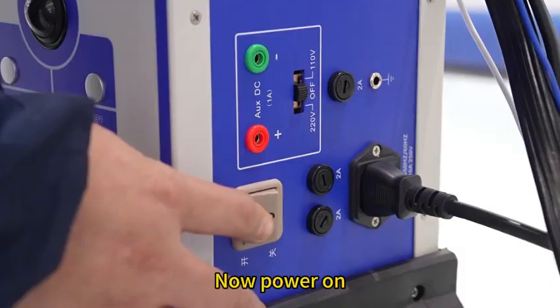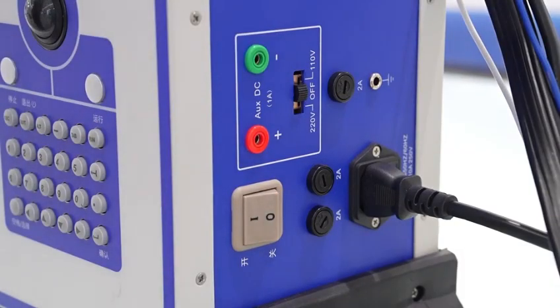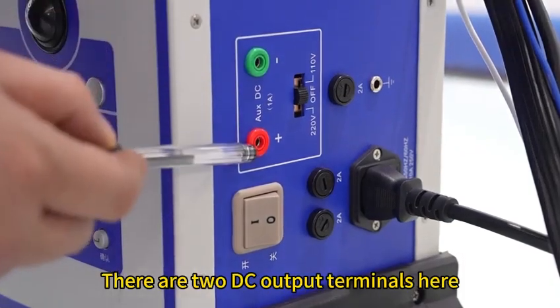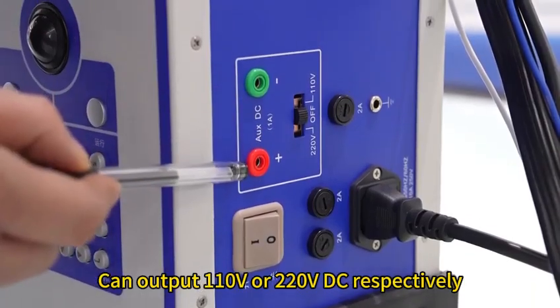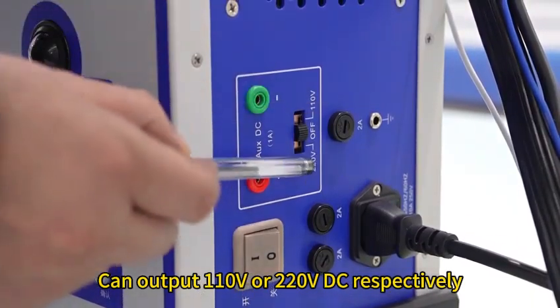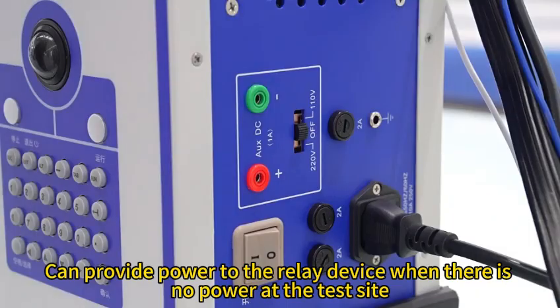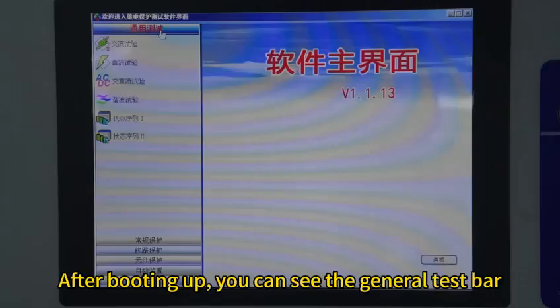Now power on. There are 2 DC output terminals here that can output 110 volts or 220 volts DC respectively. They can provide power to the relay device when there is no power at the test site. After booting up, you can see the general test bar.